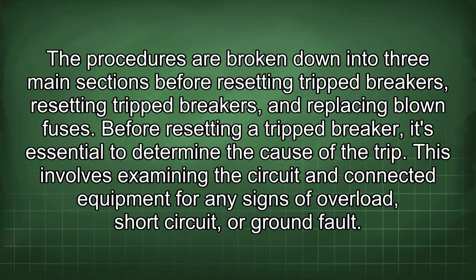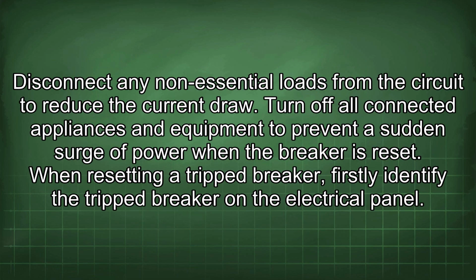Before resetting a tripped breaker, it's essential to determine the cause of the trip. This involves examining the circuit and connected equipment for any signs of overload, short circuit, or ground fault. Disconnect any non-essential loads from the circuit to reduce the current draw. Turn off all connected appliances and equipment to prevent a sudden surge of power when the breaker is reset.